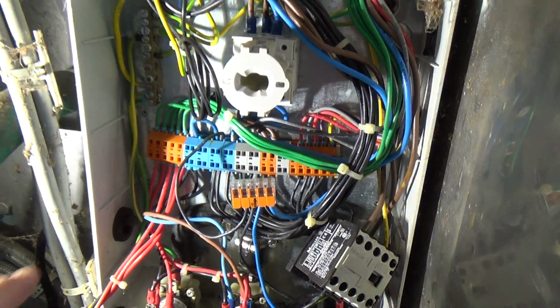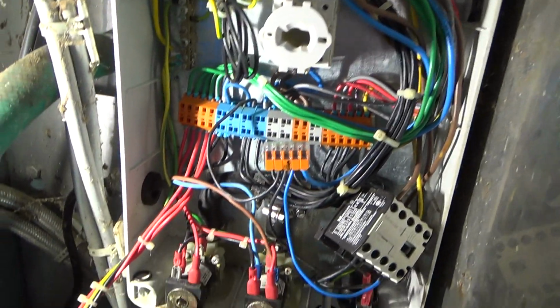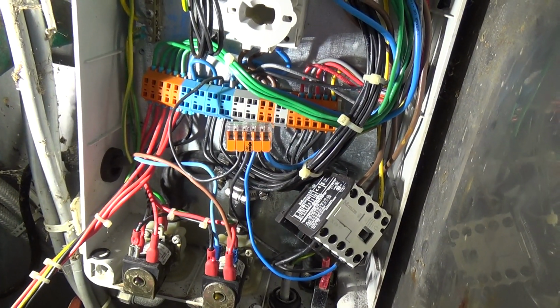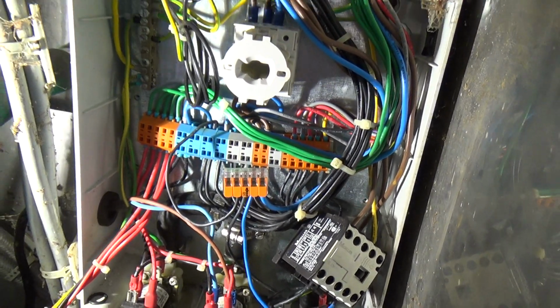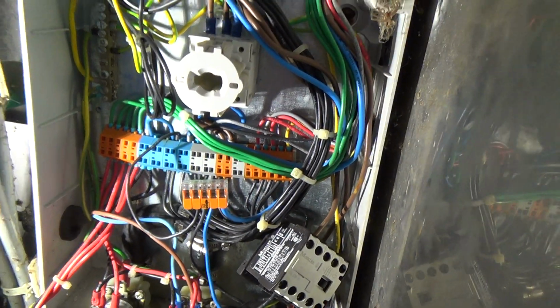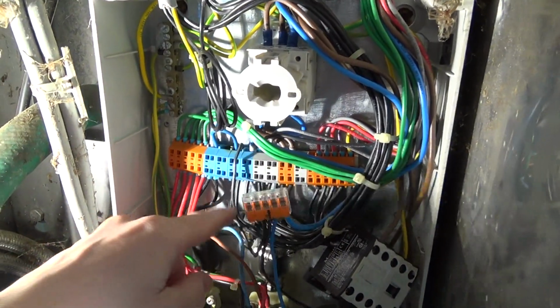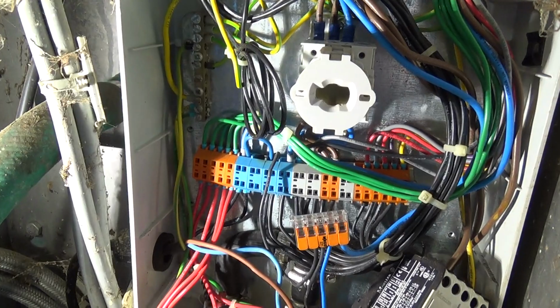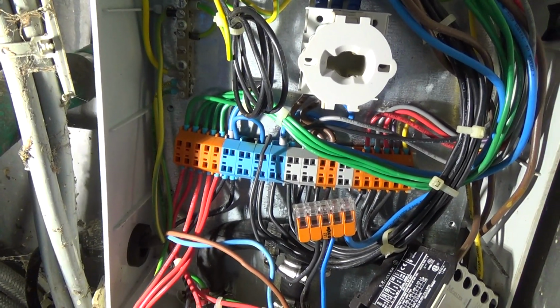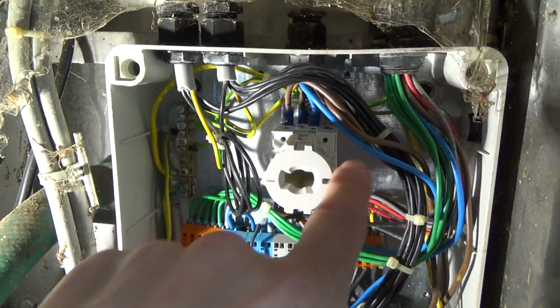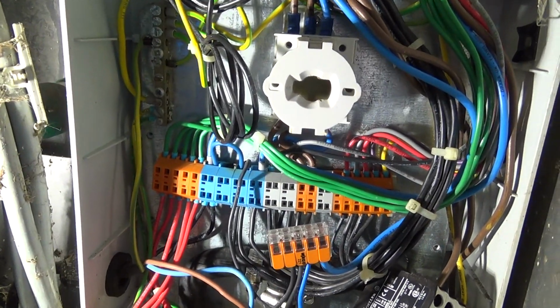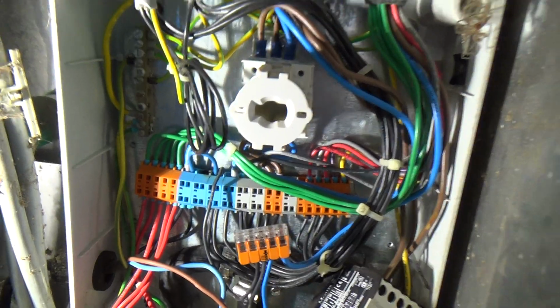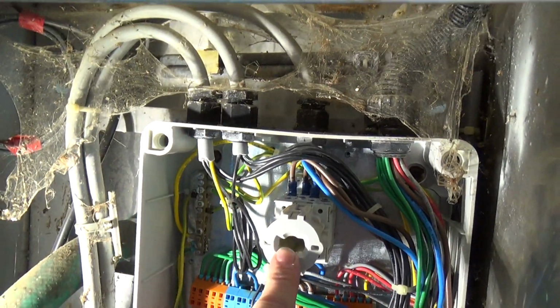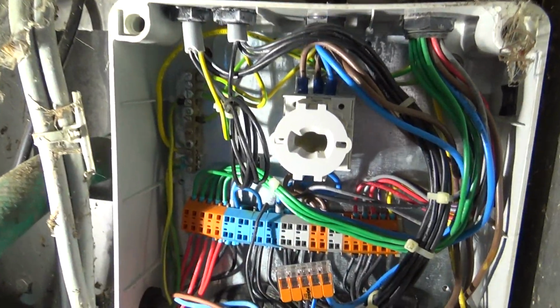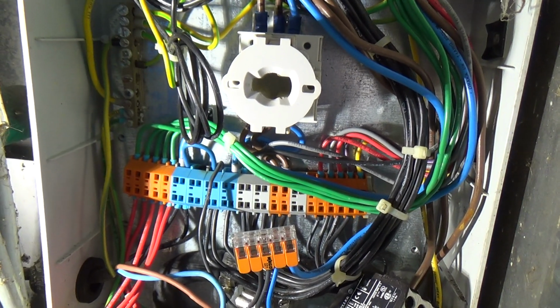So anyway, what we're going to do, I think, is I won't video it because it'll be boring, I'm just going to Megger test all the terminals that I can get to, just to make sure there's nothing on the tank that looks earthy, but I think we were just chasing a fault that wasn't there because somebody's done that without fully realising what the implications were of their bodging. When you turn this off, it should isolate the box. I mean, really, what they should have done was this incoming cable should go straight to that switch and not even bother going into that little mini DIN rail thing there.